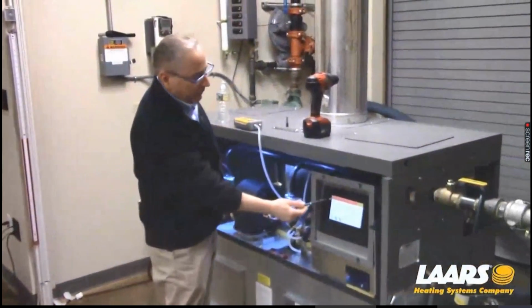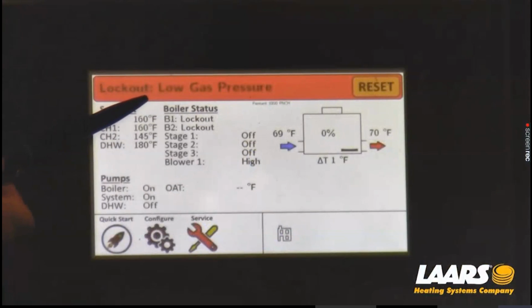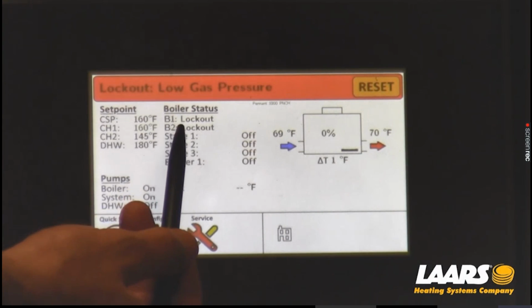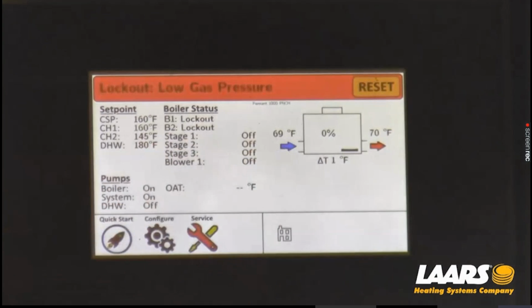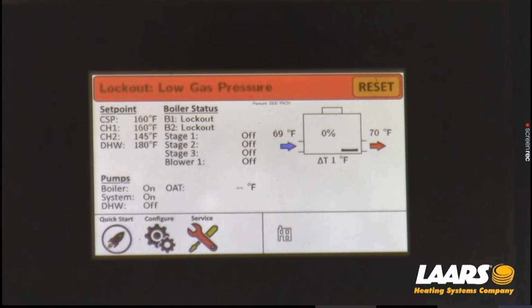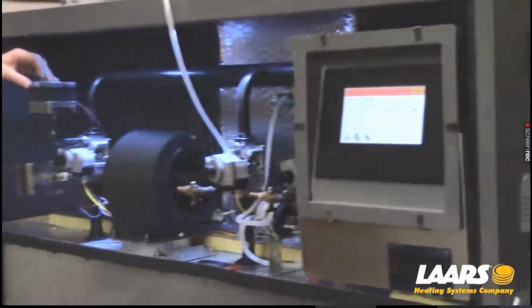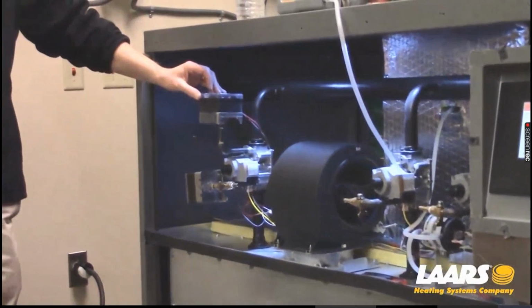So the very first thing we'll see is lockout. So it's telling us the boiler's locked out. I haven't called for heat, but I'm in lockout. It says reset. You can reset it there, but it's telling me what the lockout is: low gas pressure switch. Even if I reset it there, it will not fire the boiler. The reason is, my low gas pressure switch, which is right here, is in lockout.